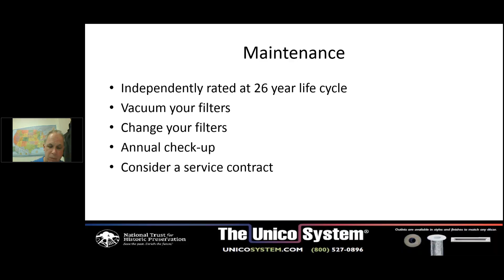The contractor who installed it will want some sort of service contract or maintenance agreement with you. Generally, as part of that, they change your filters once or twice a year when they come for your annual checkup. I strongly recommend people take a service contract. We see them anywhere from $200 to $500 a year per system on average. It's also for emergency call-outs. Generally they do a clean and check of all the equipment in spring and fall, change the filters, make sure there are no clogs, that sort of thing. It's well worth doing—an inexpensive investment to make sure your system continues to run exactly as it did on the day it was installed and signed off to you.